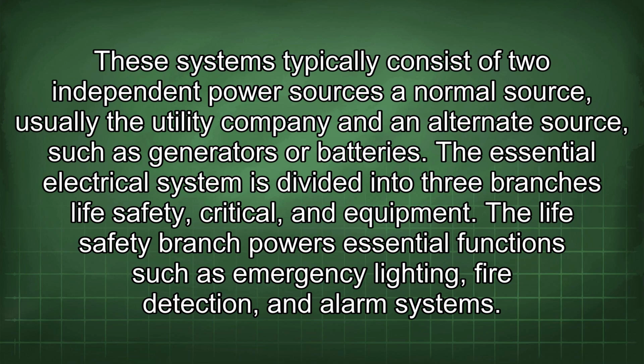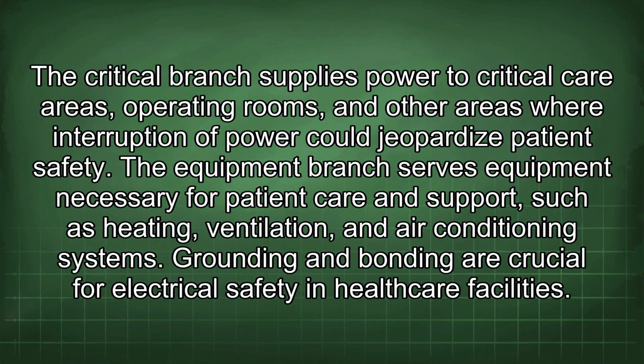The essential electrical system is divided into three branches: life safety, critical, and equipment. The life safety branch powers essential functions such as emergency lighting, fire detection, and alarm systems. The critical branch supplies power to critical care areas, operating rooms, and other areas where interruption of power could jeopardize patient safety. The equipment branch serves equipment necessary for patient care and support, such as heating, ventilation, and air conditioning systems. Grounding and bonding are crucial for electrical safety in healthcare facilities.